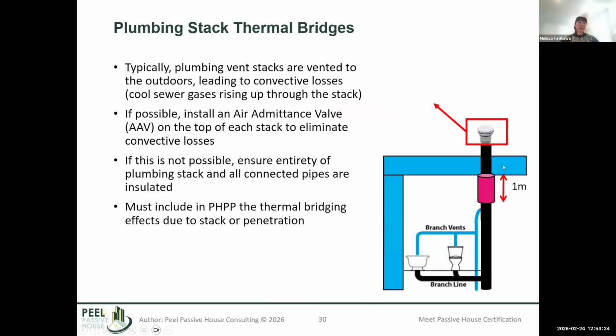Plumbing stacks in buildings are typically vented toward the outdoors, and when they're open to the sewage line below, there's a lot of convection loss happening because air is just traveling through these pipes. We often recommend, if possible, to put an AAV, an air admittance valve, on the top of the stack so that you're at least eliminating the convection losses. There'll still be a point thermal bridge through the roof, but the convection losses are the big piece.